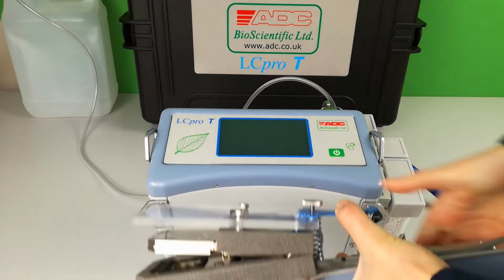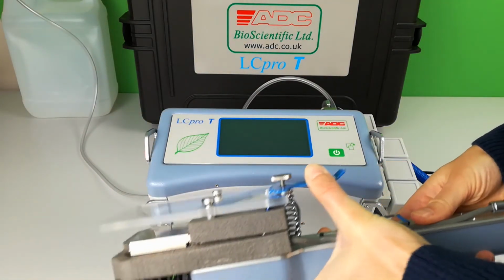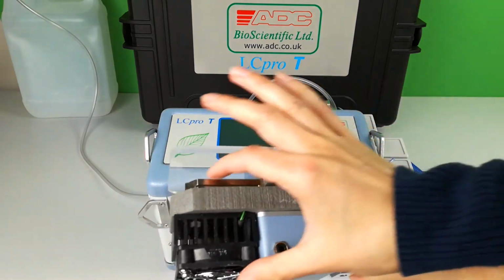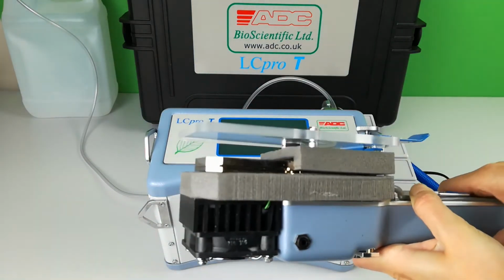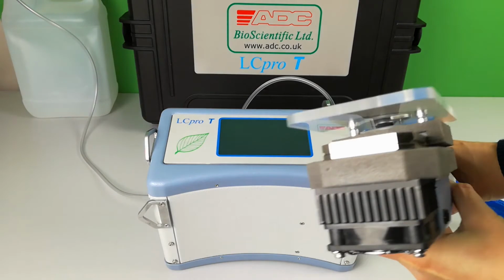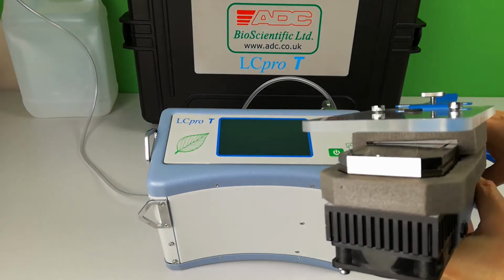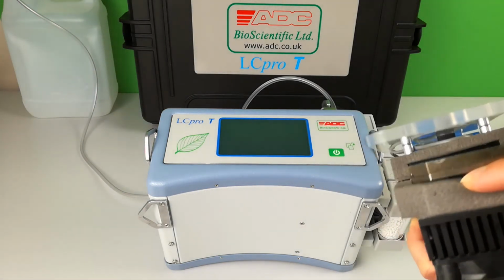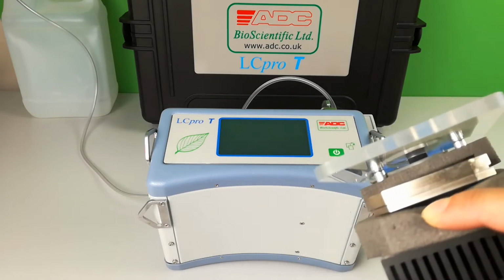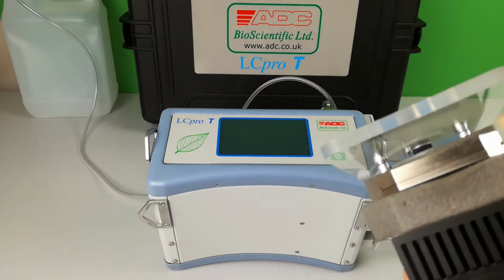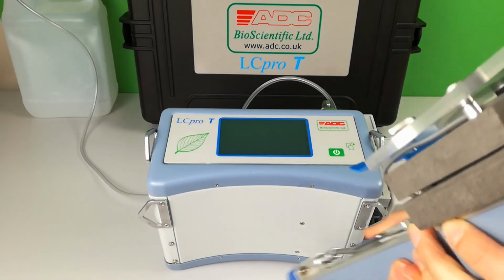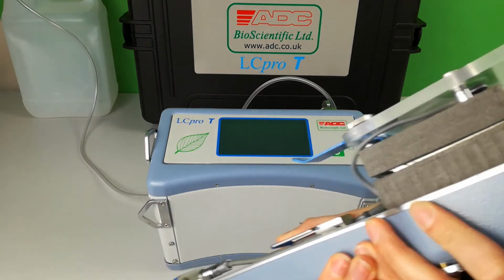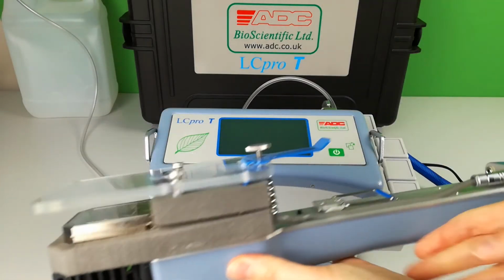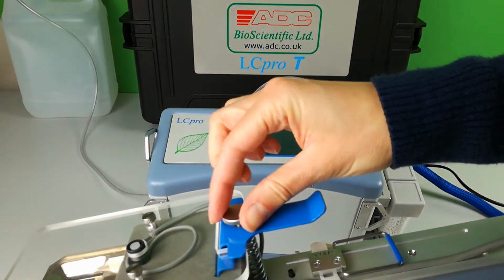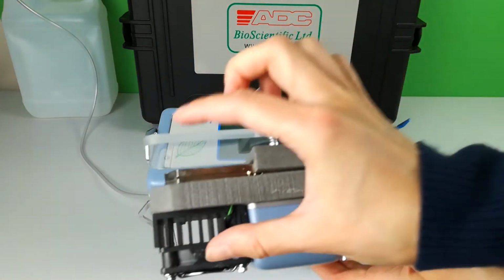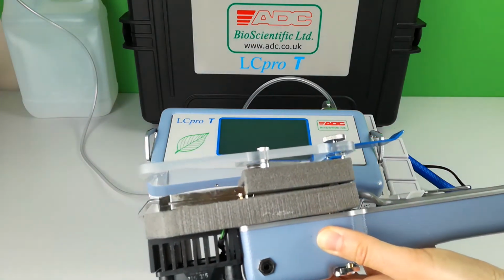Release the clip to close the jaws and check that there is no gap between the 2 sets of foam gaskets. This can be seen by pushing down the insulation foam and checking to see if any light can be seen between the 2 pieces of foam. A spring tightening or loosening tool allows you to adjust this gap if there is one to be found.